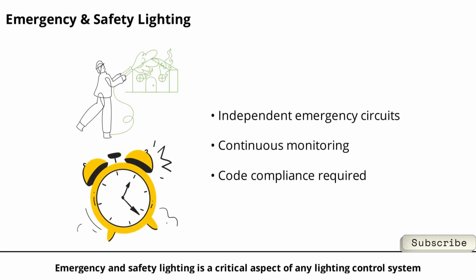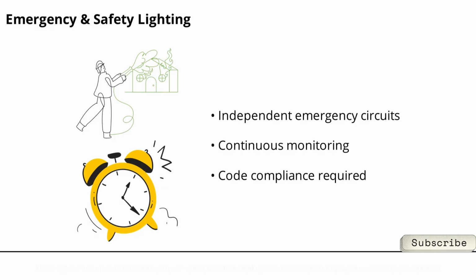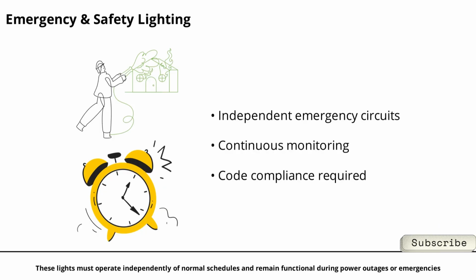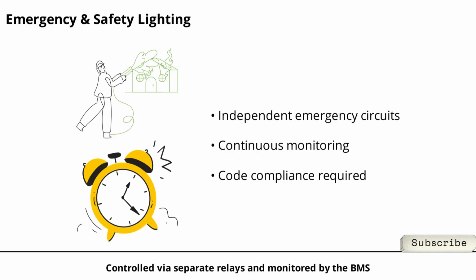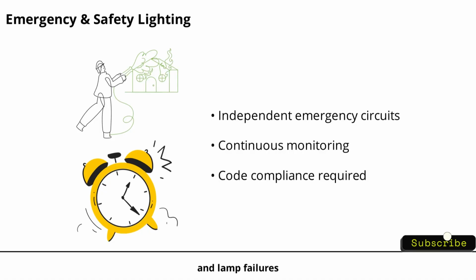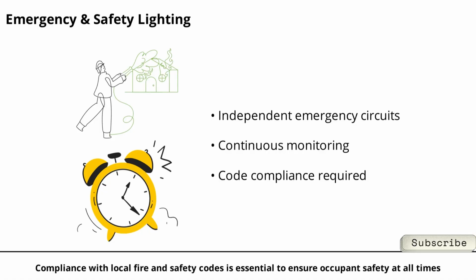Emergency and safety lighting is a critical aspect of any lighting control system. These lights must operate independently of normal schedules and remain functional during power outages or emergencies. Controlled via separate relays and monitored by the BMS, emergency lighting systems are checked for battery faults, failed test sequences, and lamp failures. Compliance with local fire and safety codes is essential to ensure occupant safety at all times.